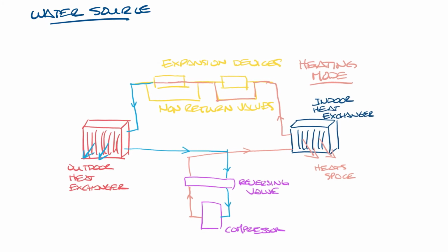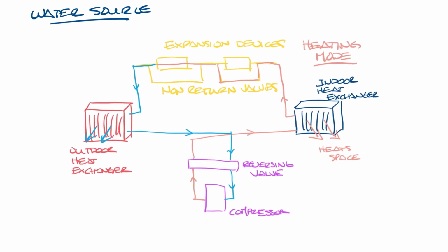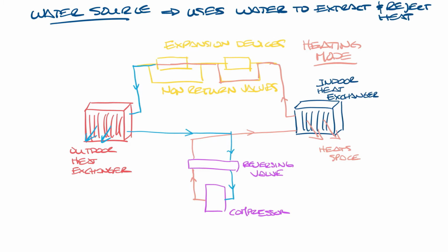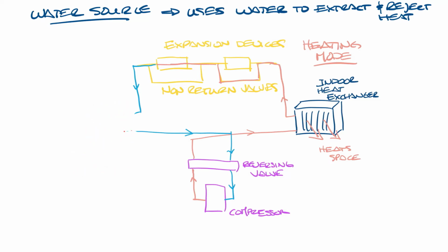Now let's move this over and let's look at a water source heat pump. Let's bring back the heat pump drawing again. A water source heat pump uses water instead of air to extract and reject heat. So instead of running the refrigerant through a coil and using a fan to blow air over it to extract or reject heat, there's a water loop that works as a refrigerant to water heat exchanger. To look at how this works, let's erase this outdoor heat exchanger. So let's look at the water loop.